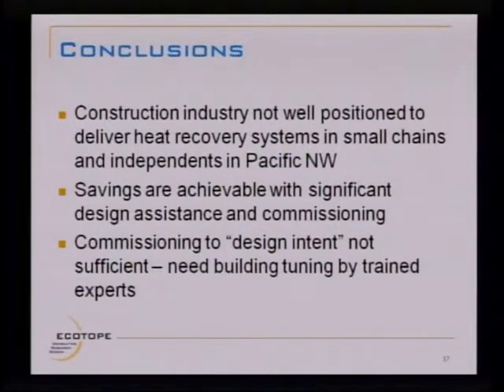And the last point there is that commissioning to the design intent is perhaps not enough. There really has to be this additional step in complex buildings that could be called building tuning. That's what I'm calling it now. It could be called recommissioning. It could be called measurement and verification. But somebody has to go back a year later and really look at the energy bills and what's going on in that store if we expect buildings to continue to function well, or even to function well to start with.